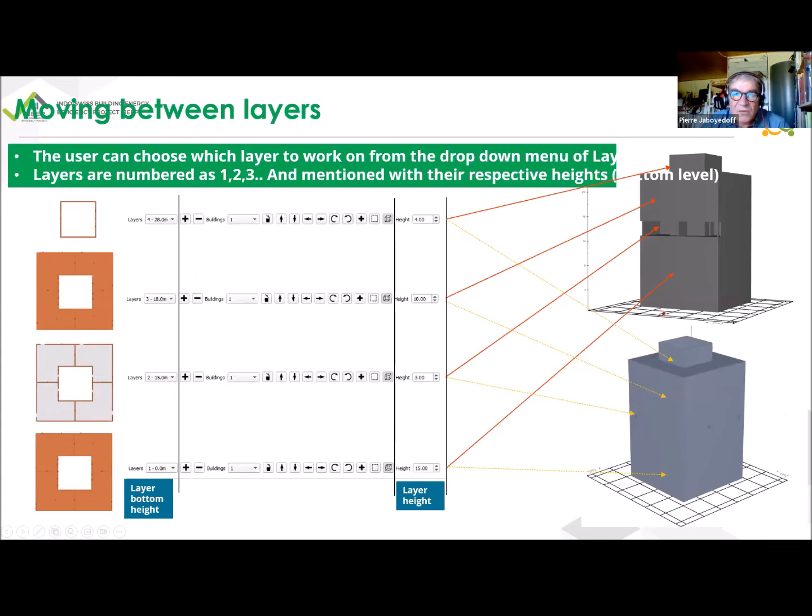And then you can calculate how much airflow would come through the entrance, and you could do the complete modeling as well. But if you want to go fast, suppose you have a typical good distribution in the shaft and no pressure loss in the shaft, then normally if you take one flat, you already get a good approximation of what you would get with a given differential of pressure, with openings sized properly for the shaft. We have, for instance, done a project in Rajkot where we tested a system like this, and with some calibrated output exhaust from the flats, we were able to move 12 air changes per hour with a fan taking only 1 watt per square meter of each floor of the flats.